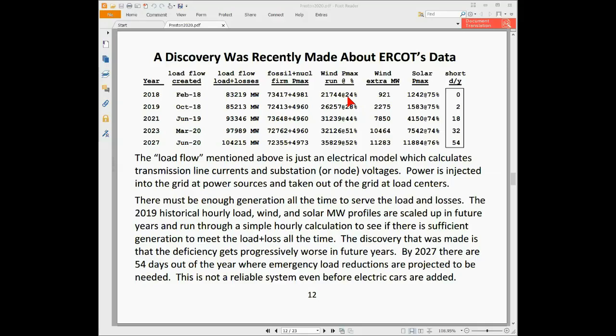Now, ERCOT does not run all the wind at 24%. They'll run coastal wind, in this case, at 58%, because there's about a 58% chance—an average—during the peak load hours that you can depend on the wind on the coast to be about 58%, but that's only 2,000 or 3,000 megawatts.